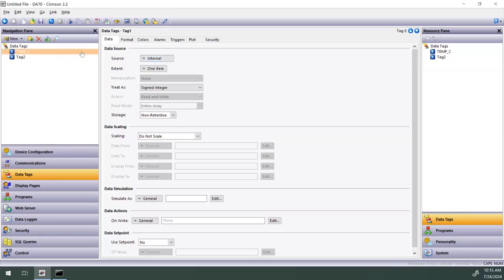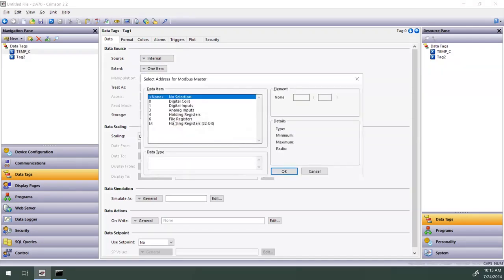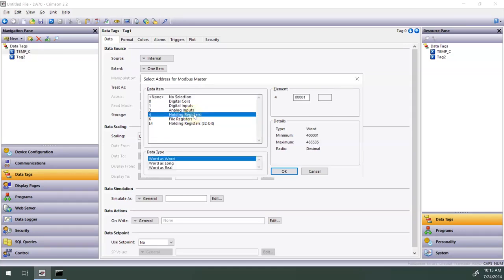And what I can do with temp C is just change the source. I can set this to ENV sensor. Once I do that, it's going to basically ask me which register I want to read. So in my case, I know I need to read holding register number 1. So this is OK, and I'll click OK.